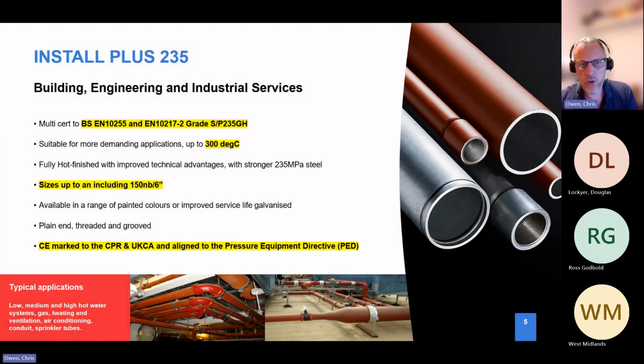We have two particular brands in the UK market. A single pipework specification is not good enough. What we have in terms of pipework standards are technical delivery conditions, which define everything from how the tube is made, its dimensions, tolerances, testing, and any marking or certification. One standard doesn't cover all requirements correctly, so we tend to reference multiple standards to give a much clearer picture of what you want from that tube and what it will do.